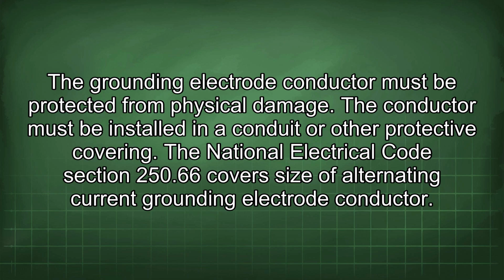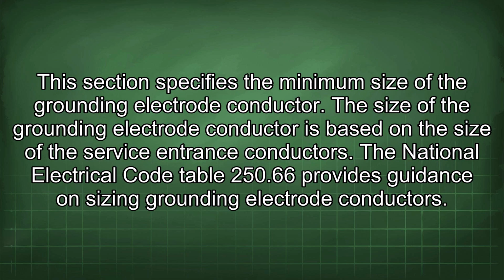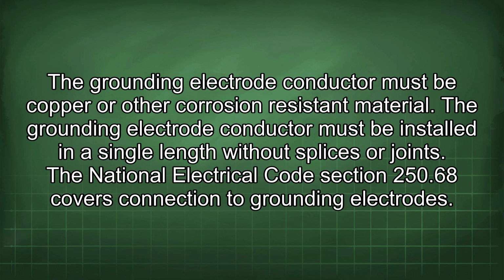The National Electrical Code Section 250.66 covers size of alternating current grounding electrode conductor. This section specifies the minimum size of the grounding electrode conductor. The size of the grounding electrode conductor is based on the size of the service entrance conductors. The National Electrical Code Table 250.66 provides guidance on sizing grounding electrode conductors. The grounding electrode conductor must be copper or other corrosion-resistant material. The grounding electrode conductor must be installed in a single length without splices or joints.